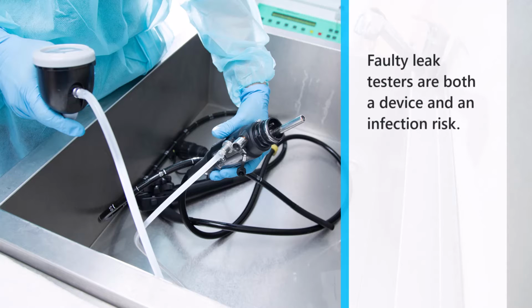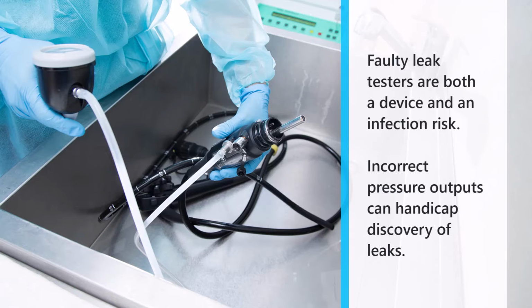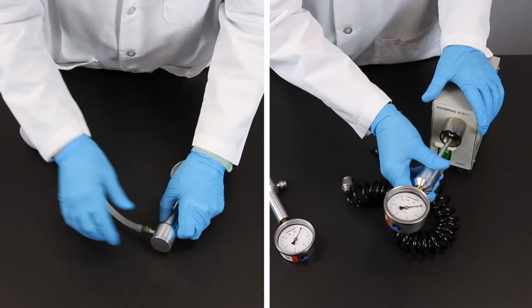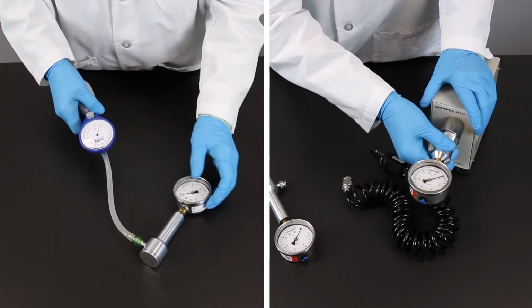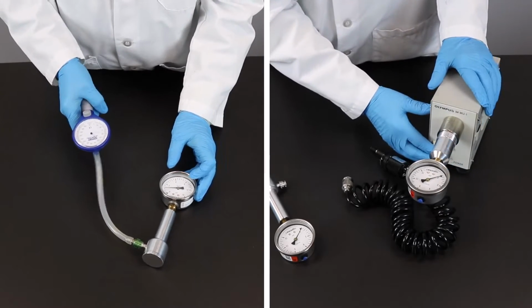Faulty leak testers are both a device and an infection risk. If a leak tester has incorrect pressure outputs, it can handicap discovery of leaks, which is a common endoscope repair issue. So that is why both handheld and automated leak testers need to be tested every day that they're used.